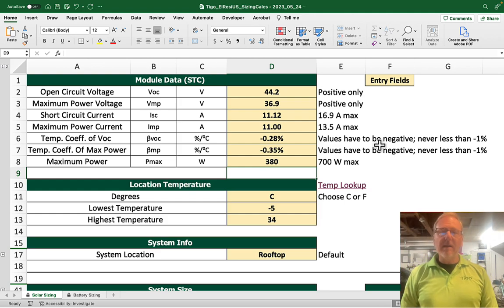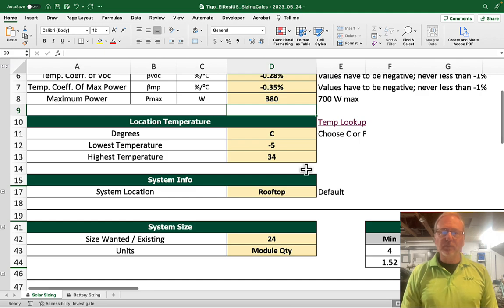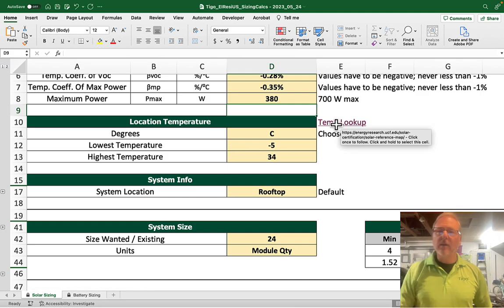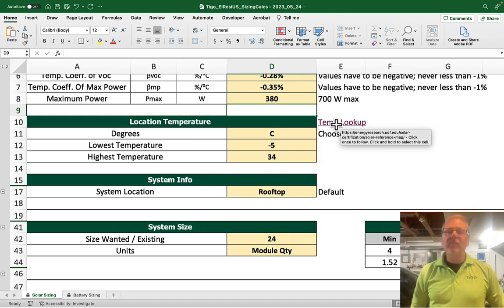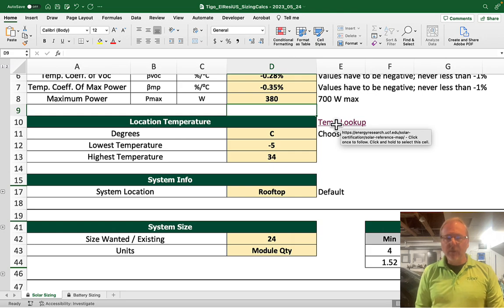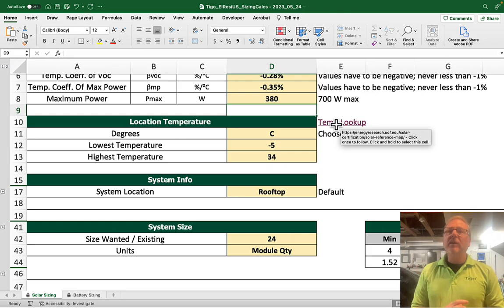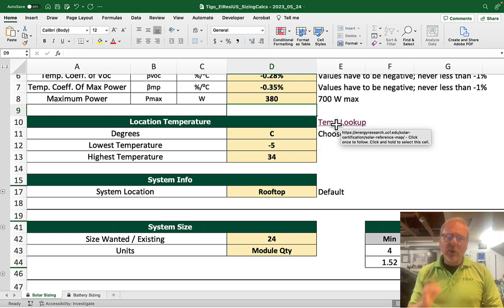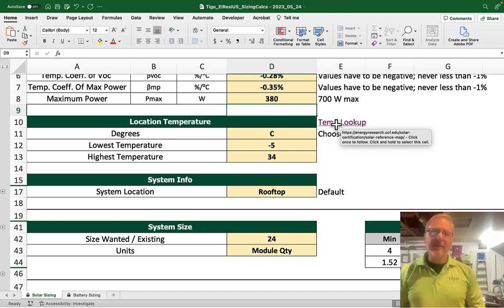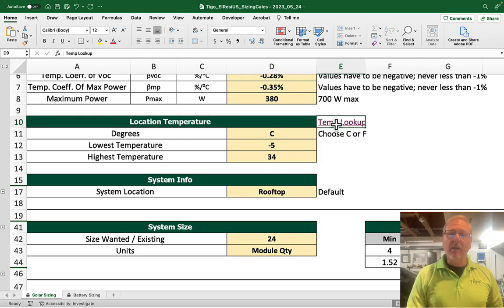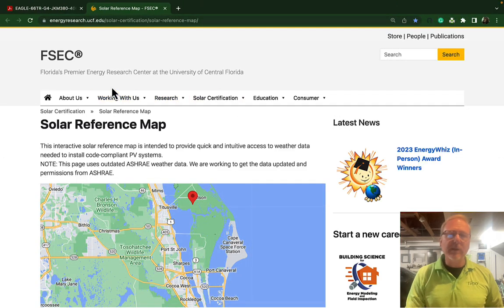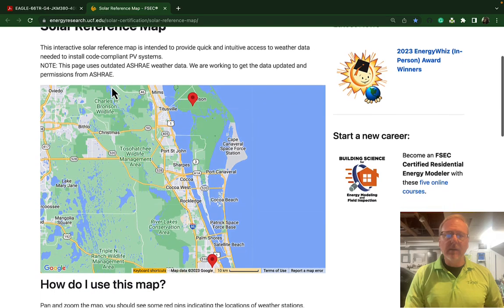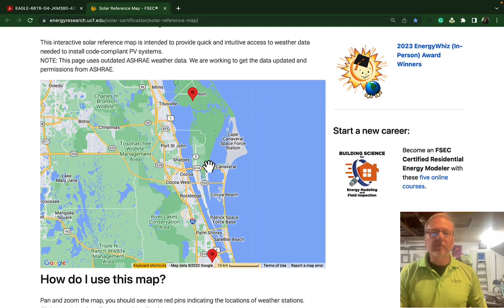We're going to go down to the location temperature. You'll see we have a link that goes to an FSEC site where we're going to grab this information. The code allows us to do this. What some people want to do is put in the record high and record low temperatures for a specific area, and that usually results in a design that is way too restrictive. Even the National Electric Code 690 says you can use ASHRAE data. So what we will do is click on that — we are taken to the Florida Solar Energy Research Center.